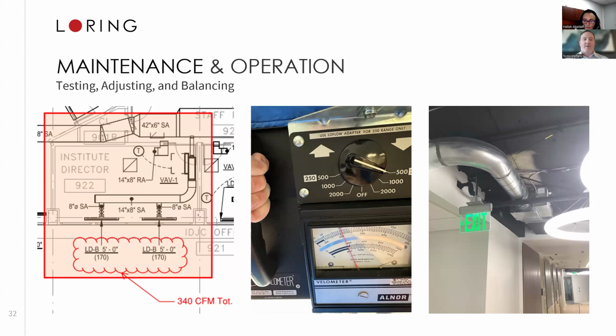So this is an example of a recent project that we were working on where we had designed a new HVAC system, and these are offices, and they're all south-facing offices. But in this case, we had designed for this institute director office 2 linear diffusers with 170 CFM each for a 340 CFM total. And that was what was on the design. That's what the contractor submitted to us in their balancing report. But they were still having temperature complaints in these spaces after they had moved in.